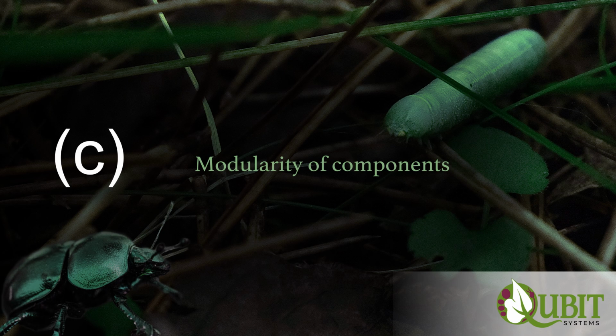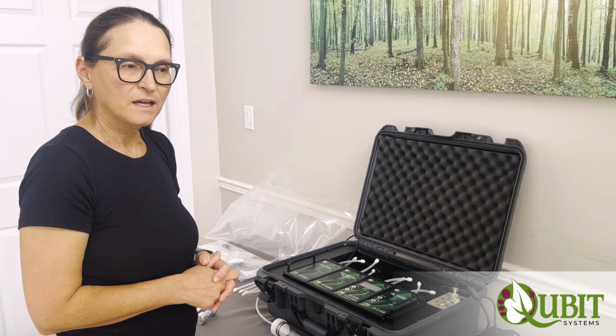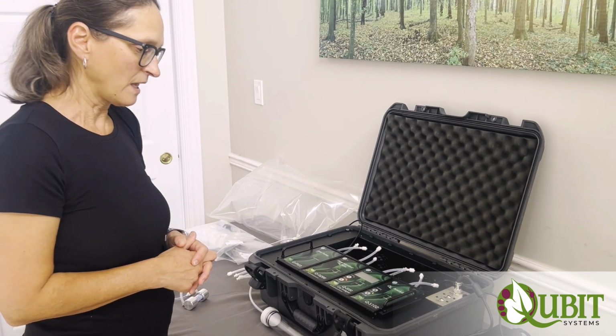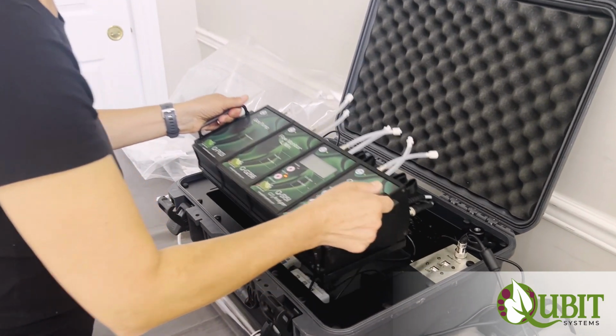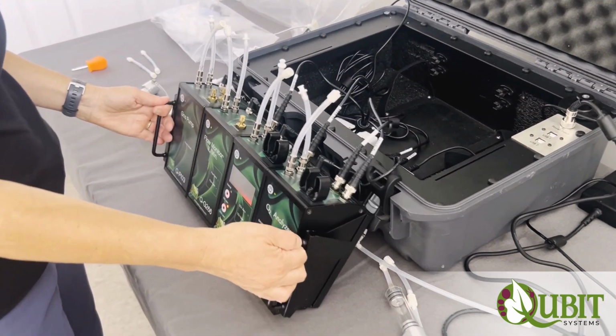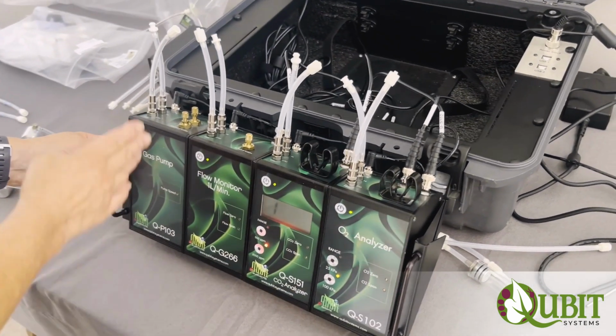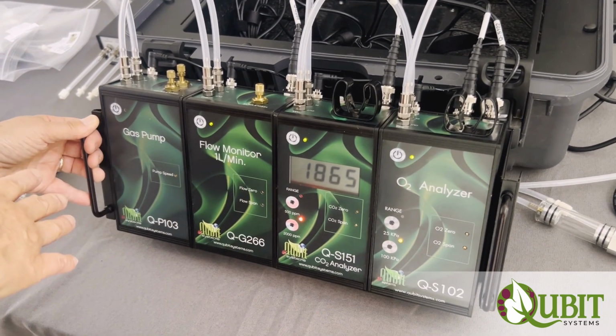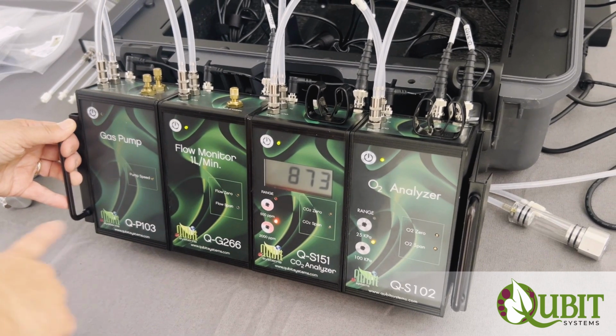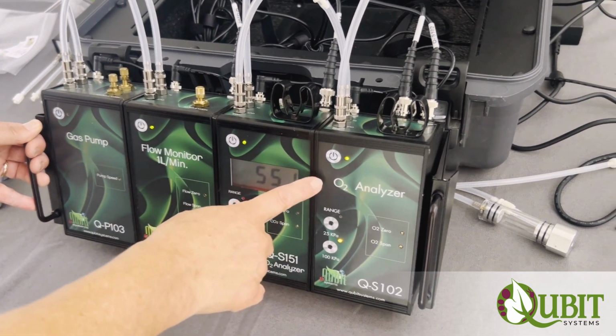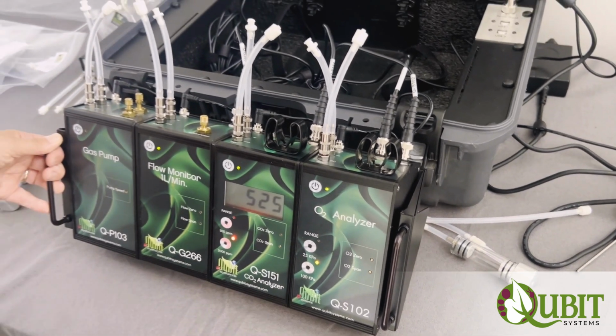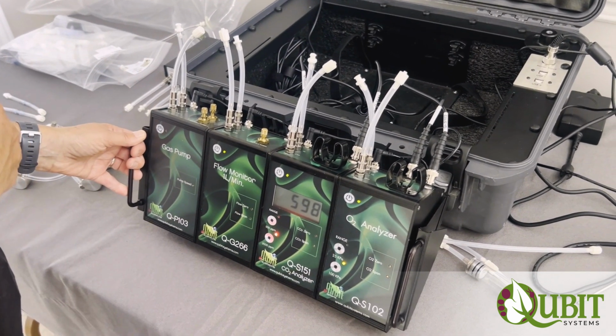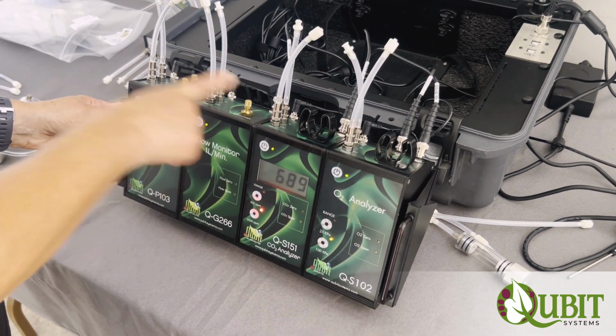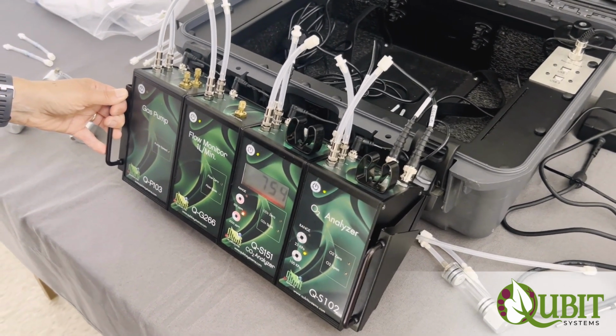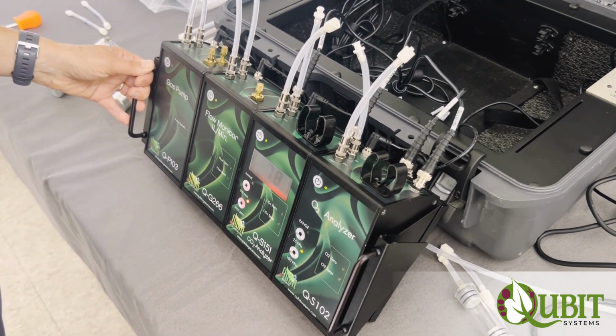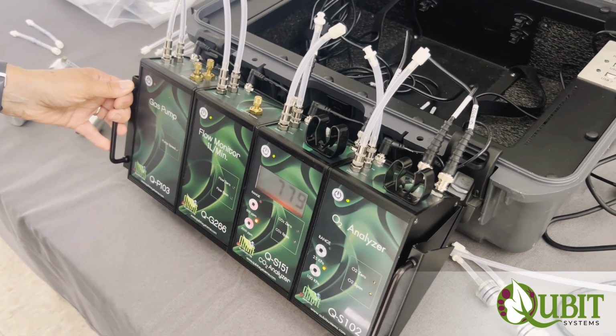The Q Box systems are modular systems, and you are able to take individual components from the Q Box and replace them with other components. So for example, in the RP1LP, we've got a gas pump P103, which is about a liter per minute gas pump. We have a 1 liter flow monitor, 2000 ppm CO2 analyzer, and a 25% oxygen sensor. However, if you're doing measurements on larger animals, more active animals, you can change the CO2 analyzer for a higher range CO2 analyzer, 5% CO2 analyzer. You can change the flow monitor for a 2 liters per minute flow monitor, and you can change the gas pump for a higher flow pump.